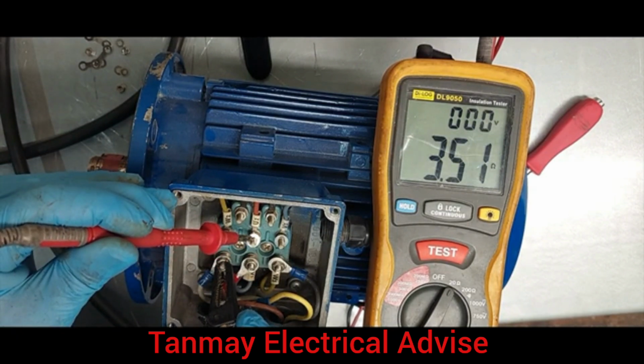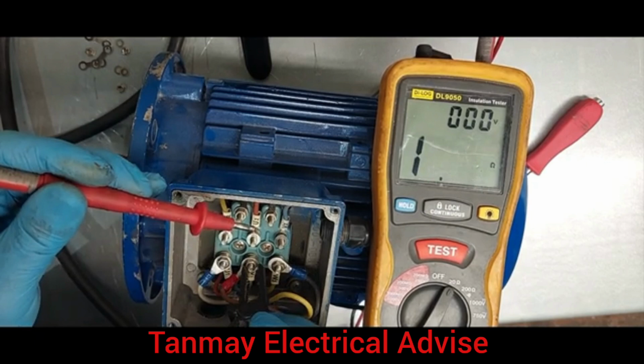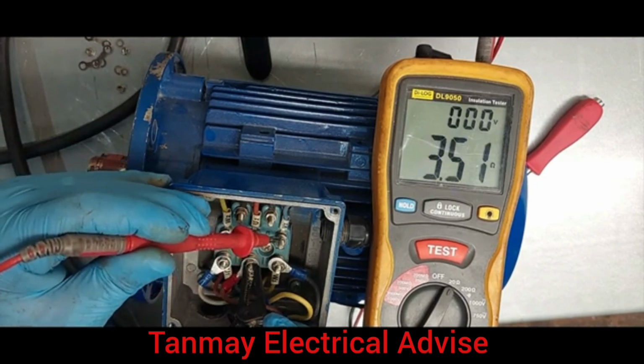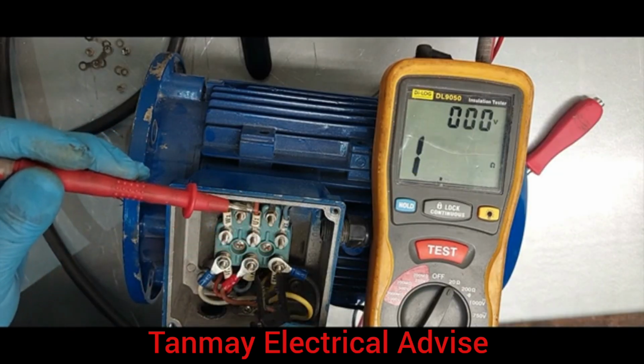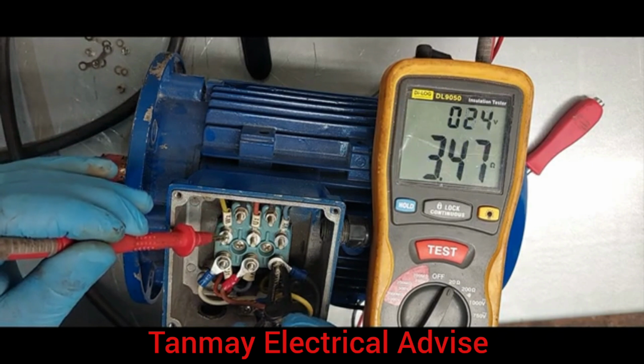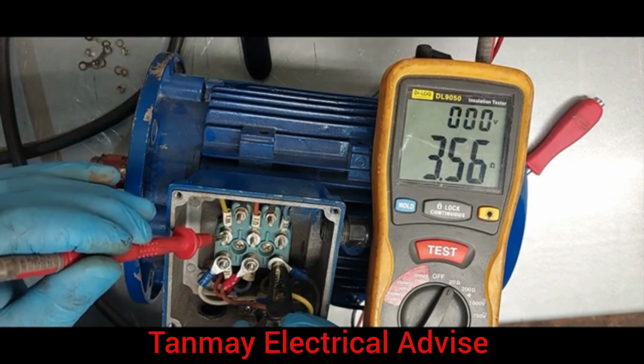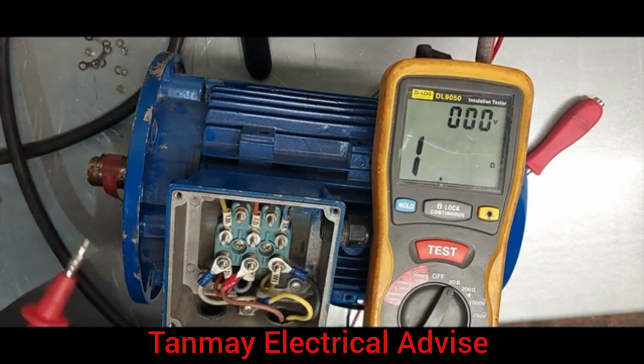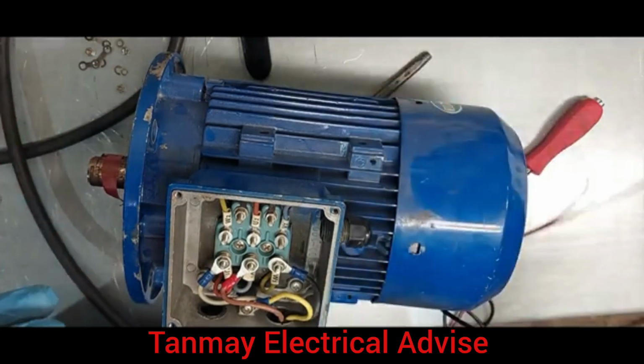Okay, V1 and V2. We have about 3.5 ohms. W1 and W2 have about 3.5 ohms. So we can see that it's all balanced. So the continuity test has been passed.